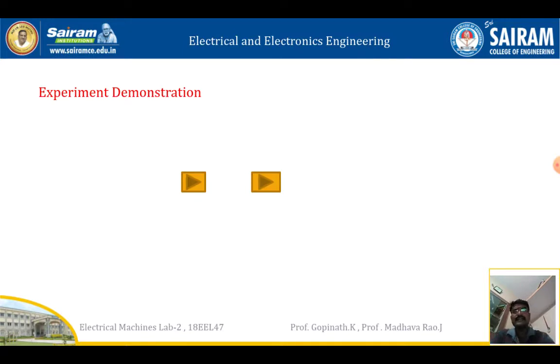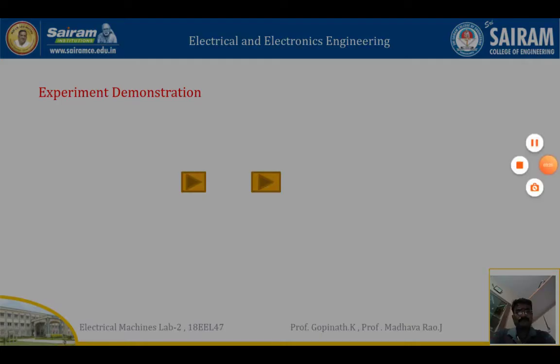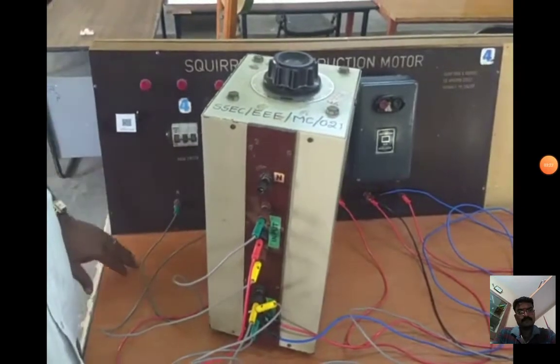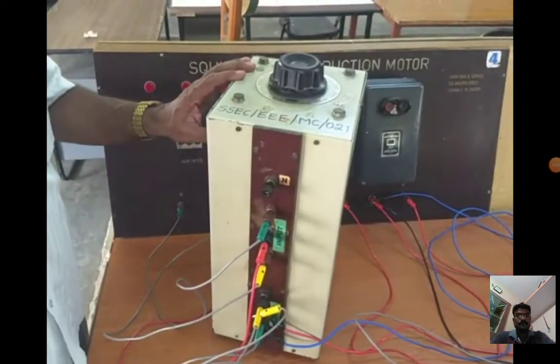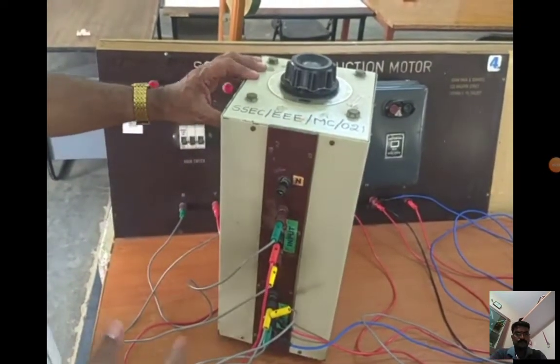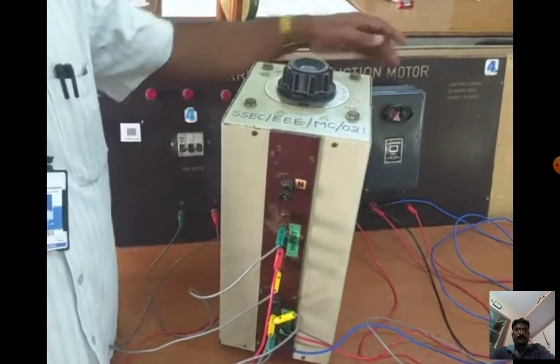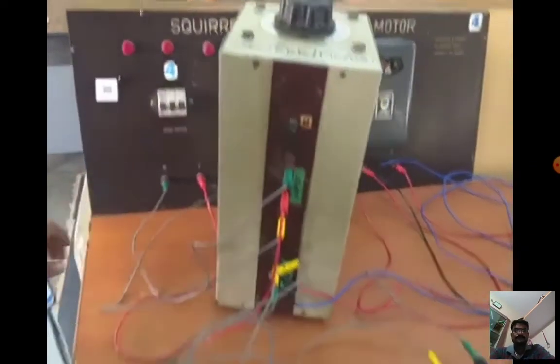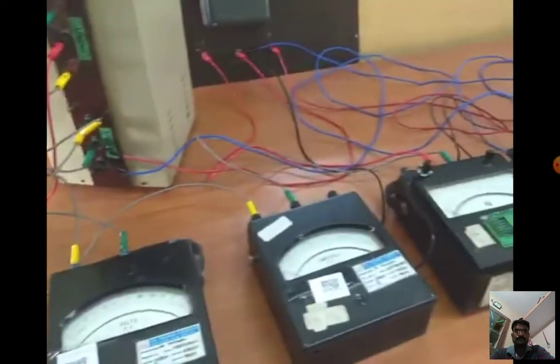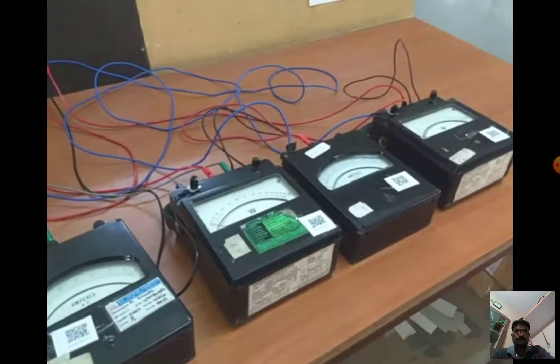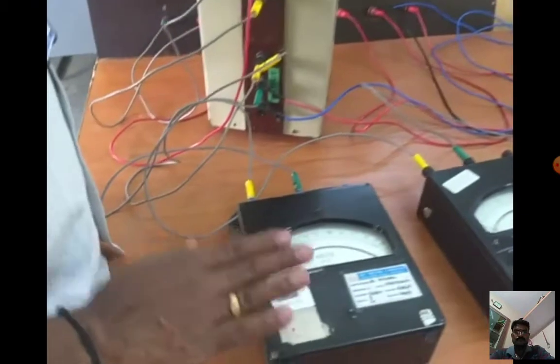Let's see the experiment demo: no load test and blocked rotor test on a 3-phase induction machine. For that, the equipment we are using is an auto transformer, a DOL starter, two ammeters, ammeter 1 and ammeter 2, two wattmeters W1 and W2, and a voltmeter to measure the supply voltage.